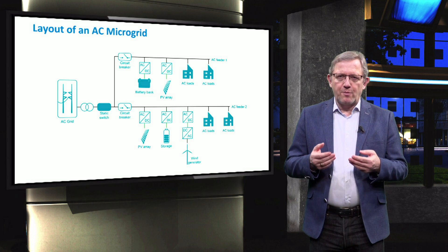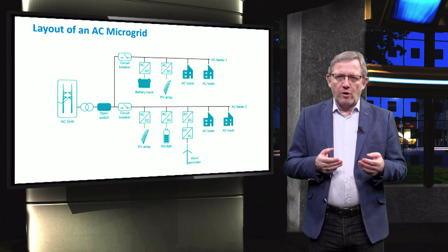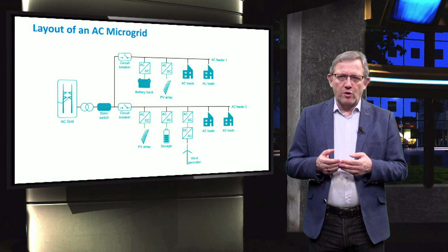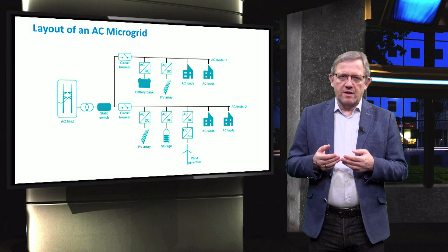The third is a solid-state transformer, which is a newly developed power electronic device substituting the conventional 50 and 60 Hz transformers employing high-frequency isolated AC-AC converters. Solid-state transformers allow connecting AC grids with a certain frequency to microgrids with a frequency different from the grid's nominal frequency. We discussed the importance and the strong and weak points of the different topologies, layouts and architecture of the microgrids.